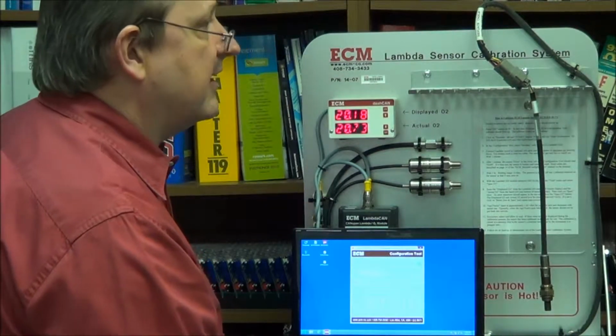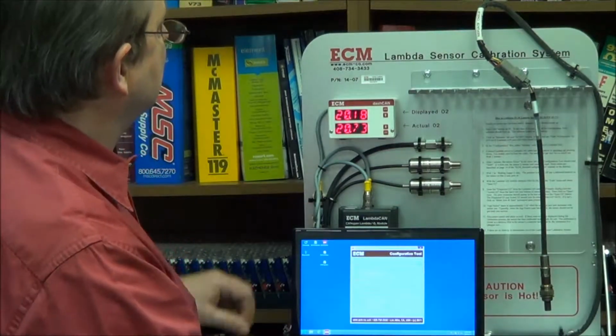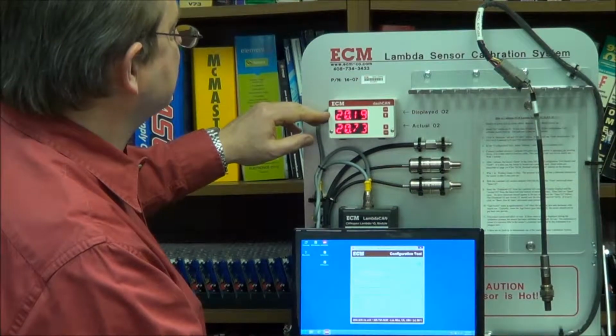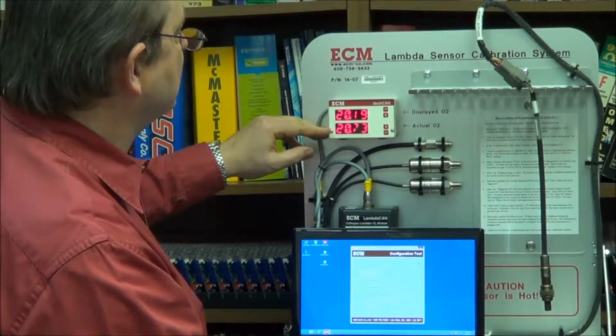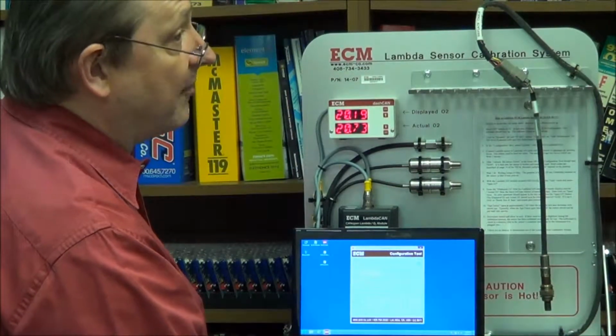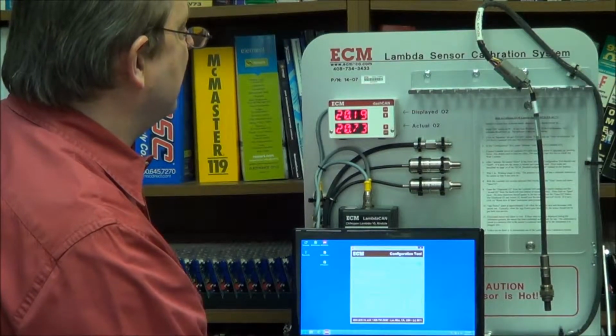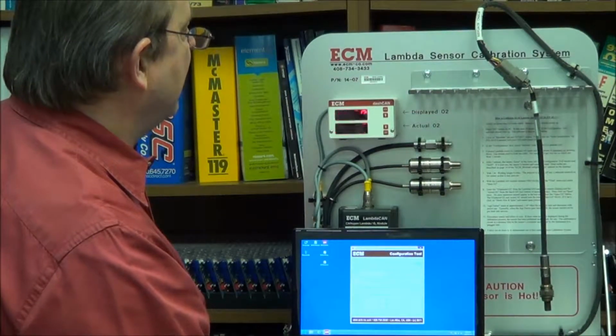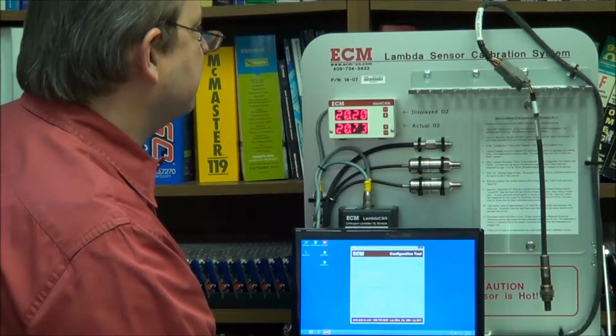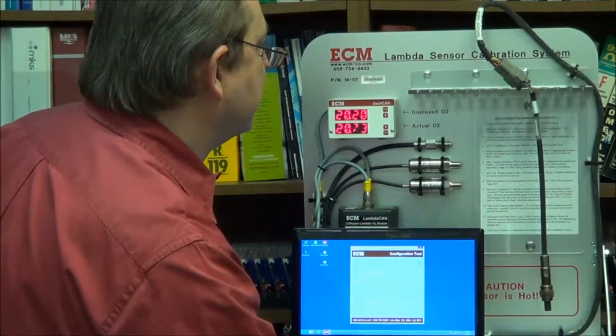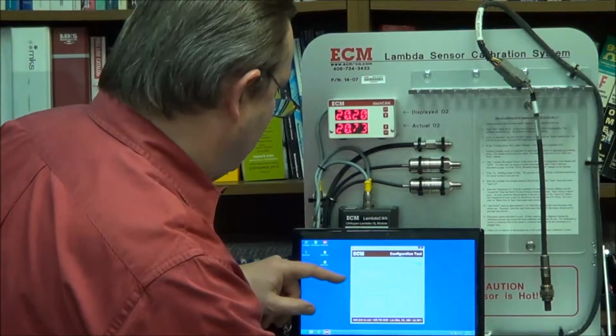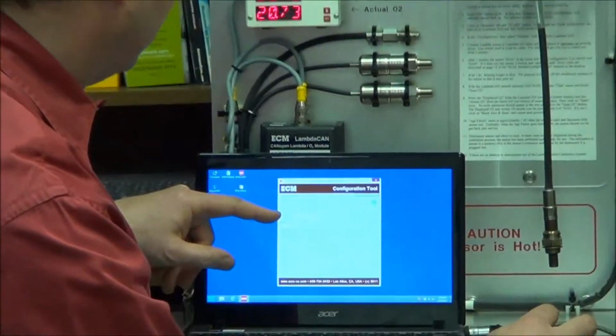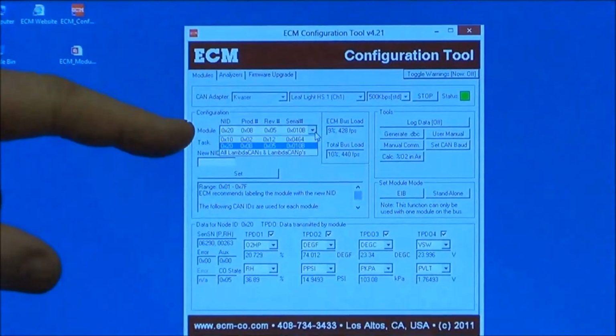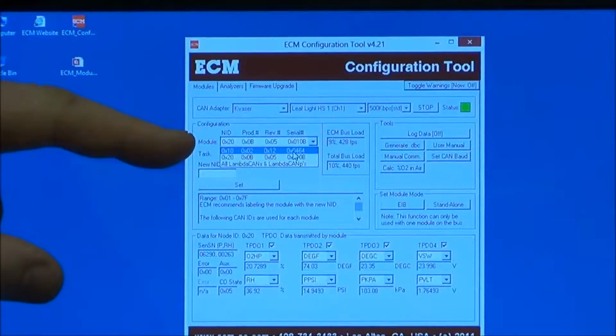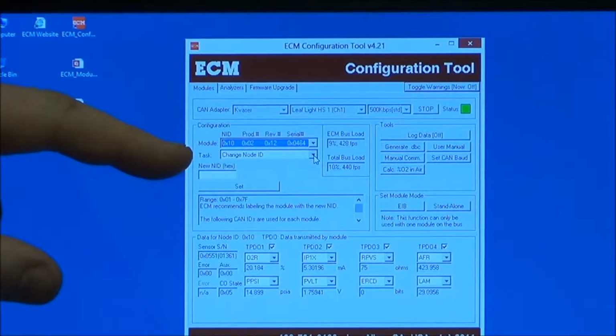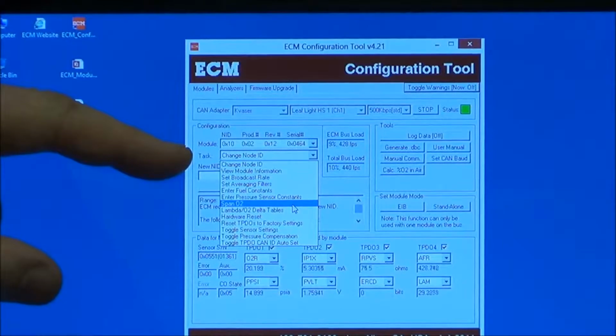All right, let's assume that an hour has passed. Note that the displayed O2 for the sensor is less than the actual O2. This is common. Typically when a sensor ages, the span goes down and this number will be less. Now let's do the calibration process. Select the module 0x10, that's the Lambda CAN module. From task, select span O2.